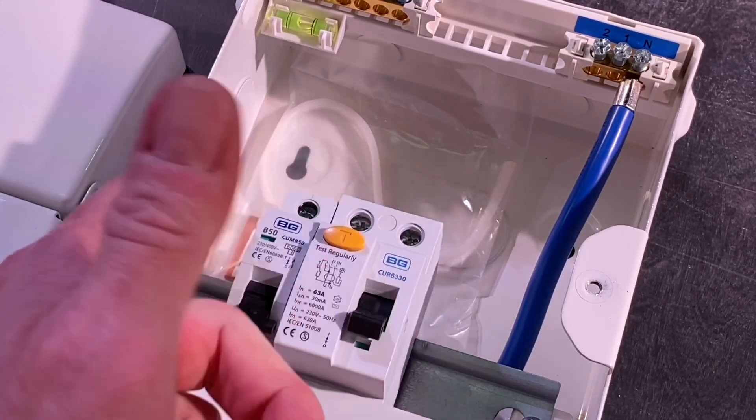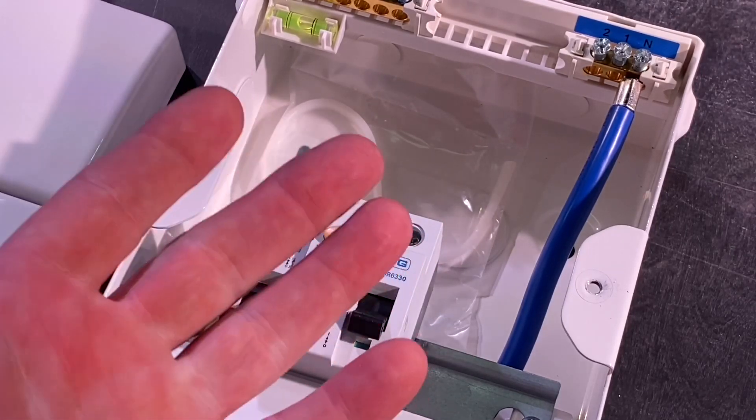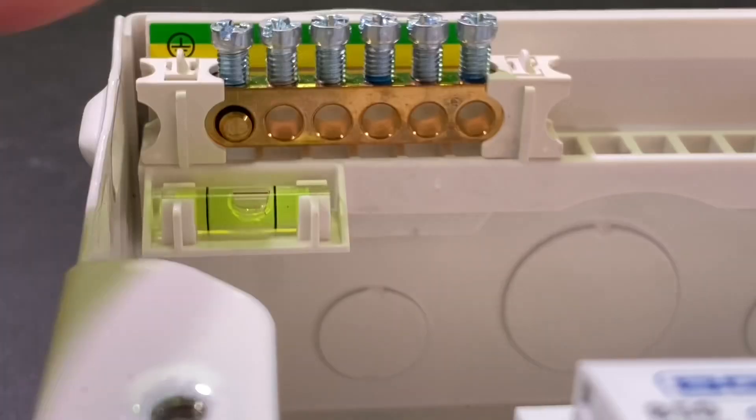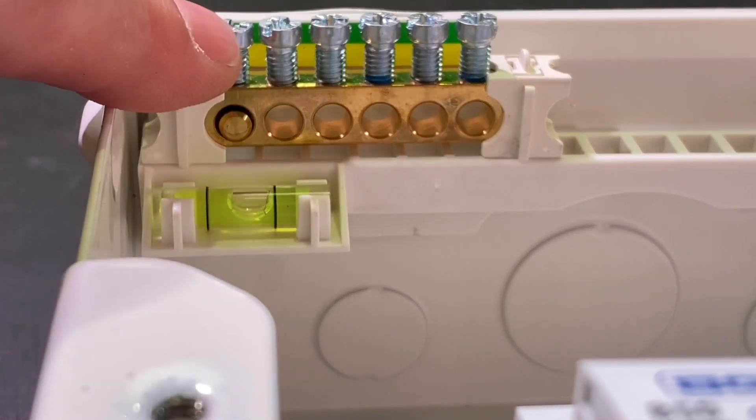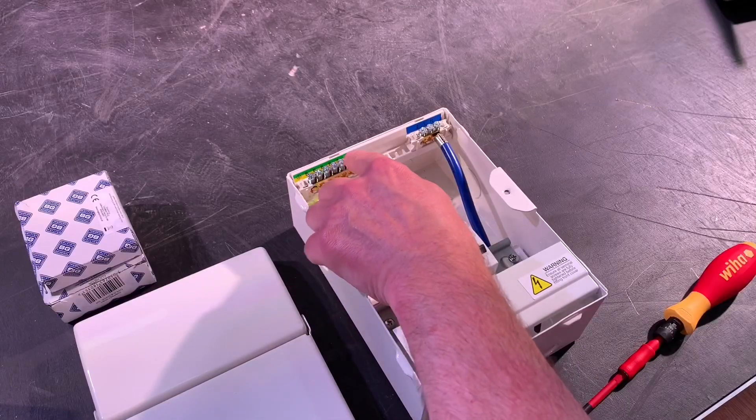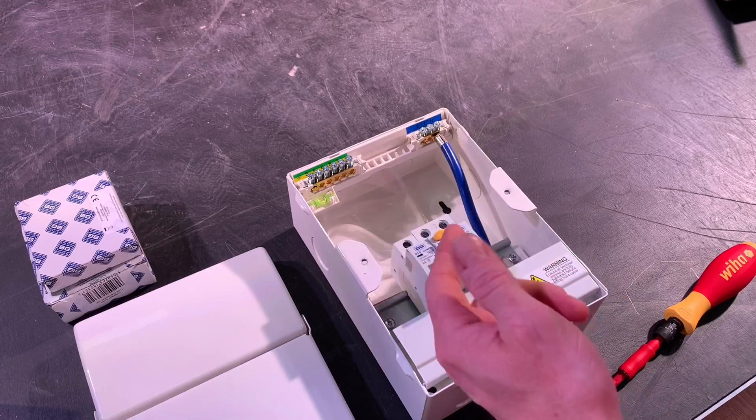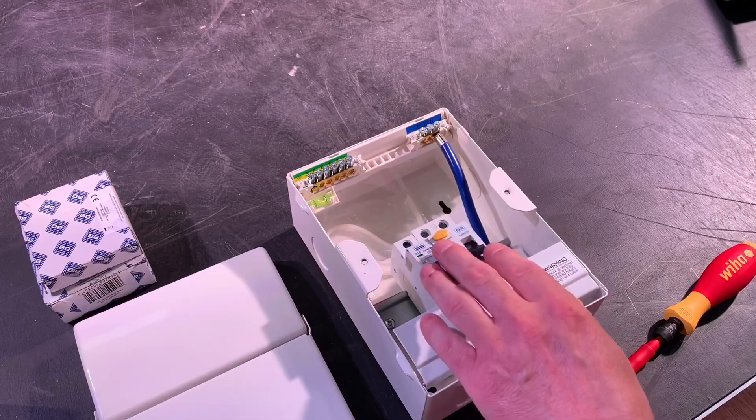The screws within here, again, all use the same screwdriver, they've all backed out. So the earth bar and the neutral bar screws are backed out and they've got those really large holes that we saw before that we really like. And look how many earth terminals you get. You could put protective bonding conductors of gas and water, the main earthing conductor and CPCs in there. They give you a lot of terminals once again.